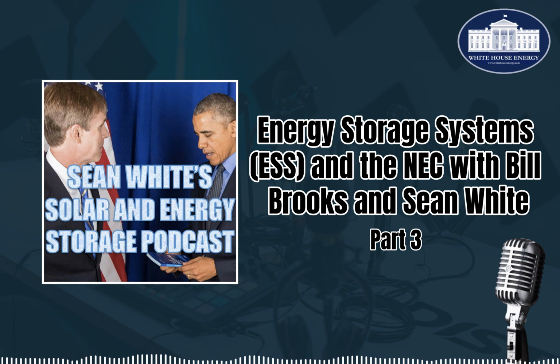Ampere interrupting capacity. So it could be in kiloamps or in amps. A lot of times we're talking about kiloamps. So 10,000 amps would be 10 kiloamps. Interrupting capacity, that would be the maximum current that you could interrupt. So it's sort of like the breakers have a range. So it could be a 40 amp breaker, it could be between 40 and 10,000. And then maybe you'll have a main breaker on the supply side of that that's going to get those higher amps there. There's short circuit current rating, fault current rating, all this.